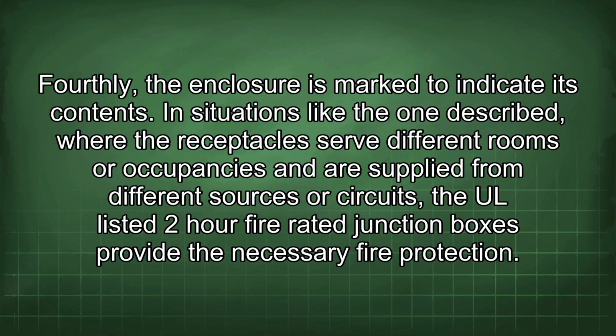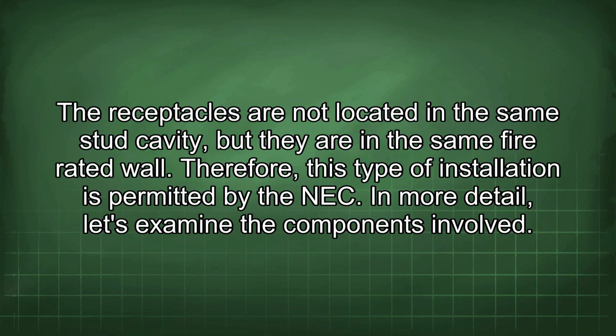In situations like the one described, where the receptacles serve different rooms or occupancies and are supplied from different sources or circuits, the UL listed 2-hour fire-rated junction boxes provide the necessary fire protection. The receptacles are not located in the same stud cavity, but they are in the same fire-rated wall. Therefore, this type of installation is permitted by the NEC.